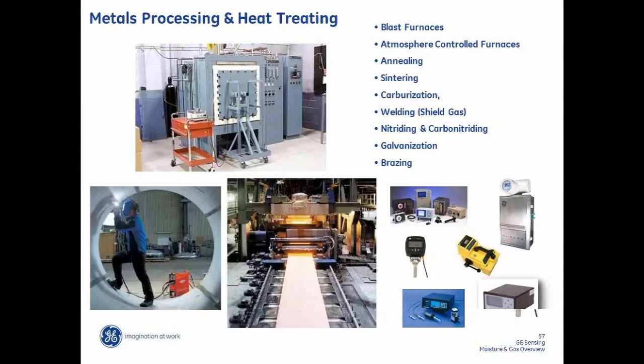And as we kind of wrap this up, we've talked about the instrumentation, but it's often very important, and just as important, to have a good sampling system, to have good measurement integrity. So we've got a lot of experience with sampling systems, and we do things like stream switching or solenoid valves for purging in cal gases, or just the regular cleanup of depressurizing a gas, filtering the gas or liquid, and regulating the flow through the sensor system.